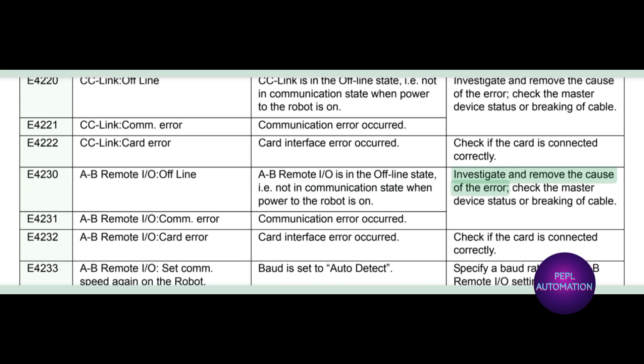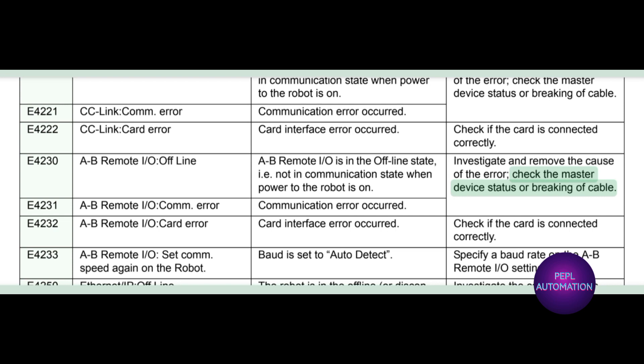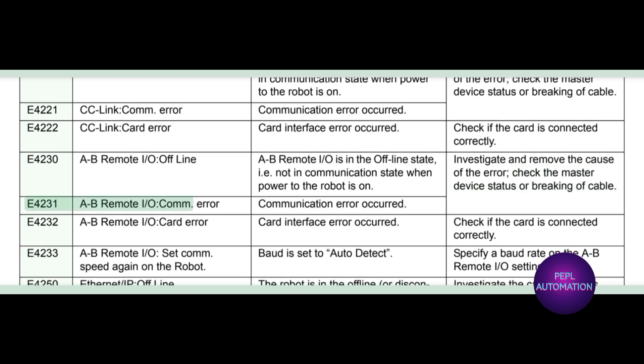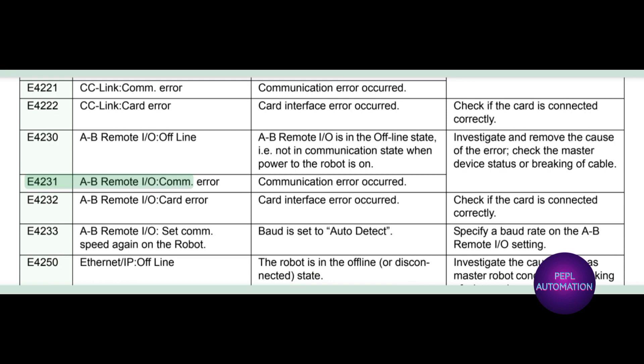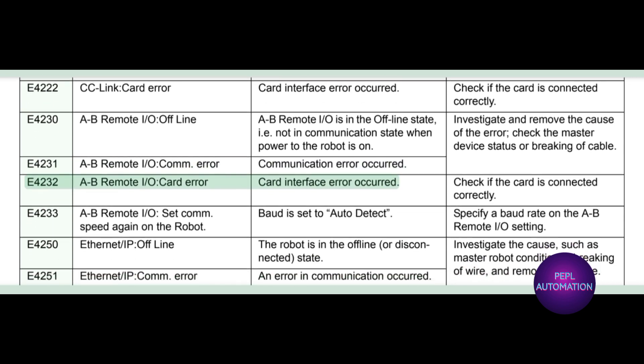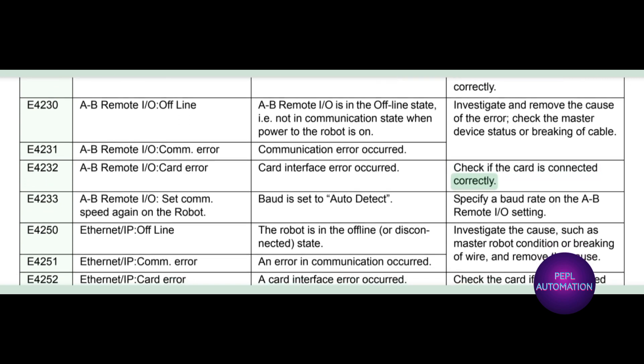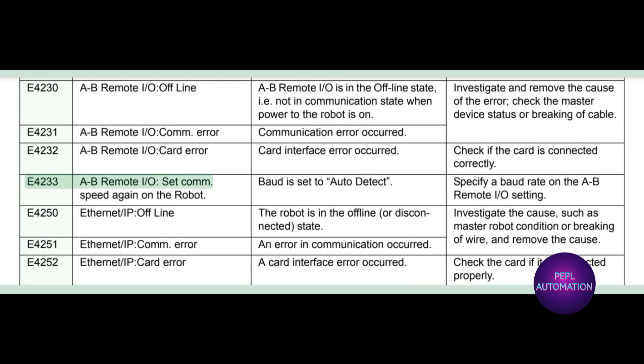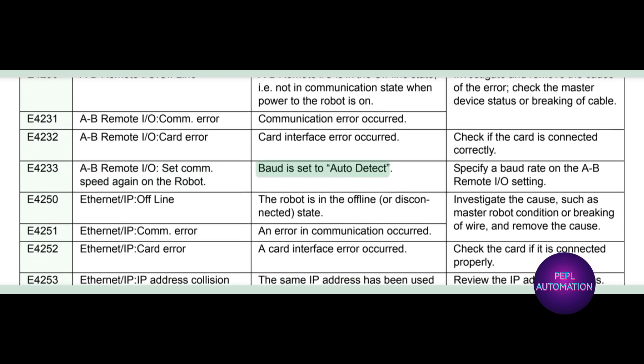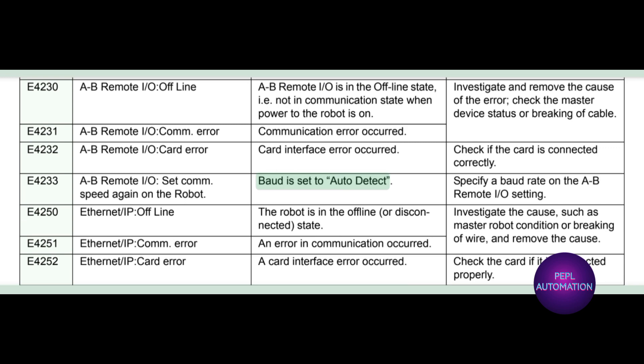Investigate and remove the cause of the error. Check the master device status or breaking of cable. E4231 AB remote IO com error: a communication error occurred. E4232 AB remote IO card error: a card interface error occurred. Check if the card is connected correctly.